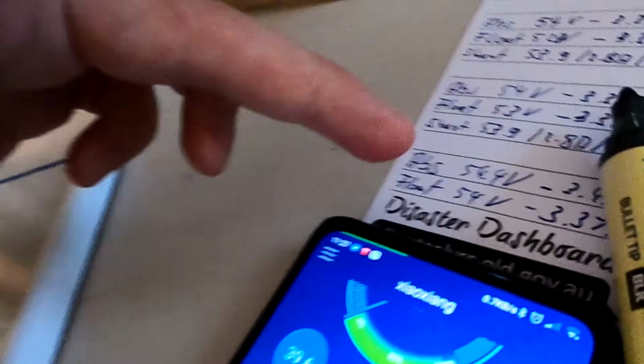This is exactly what I was struggling with the last couple of weeks, since I put this all together as a temporary setup on the workbench with the charge controller, the inverter and everything. Nobody can give you a specific answer on how to set up your charge controller, what settings are best - for example, what should you set it to? They all give rough advice, but as many people say, it all depends on your circumstances, your battery, what kind of chemistry you're using, what kind of solar you have, what kind of load you have. This is all very individual, and it's very hard to say you need to set this to 3.4 volts or 54.4 volts for absorption with a 2-hour absorption time, and that this is the right setting.